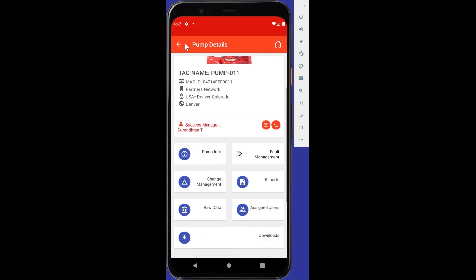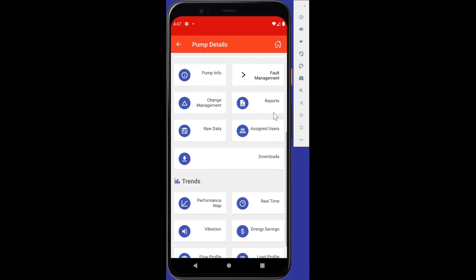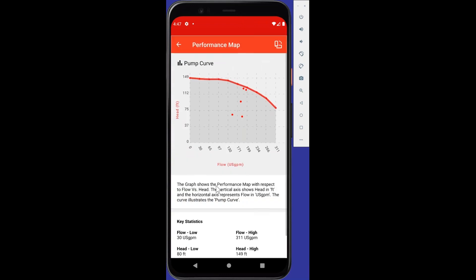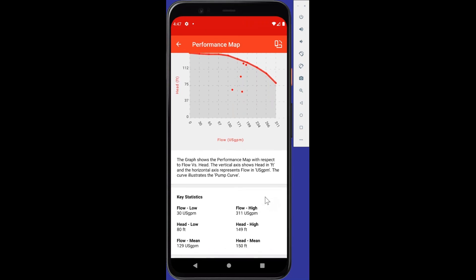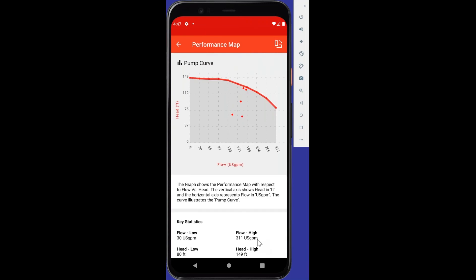I want to show you a few more features of the app. Let's scroll down to the performance map. So if I go ahead and hit performance map, we're going to show you the, well, we're all pump people on this call, the head versus flow curve map. As many of you know, our pumps send data to our cloud every five minutes. So on the graph there, you see five dots. So that's roughly what that pump's been doing over the last 25 minutes. Is my math right? Five times five is 25. Over the last 25 minutes. We see here some key statistics around the lowest flow and the highest flow and the lowest head and the highest head and the mean flow over the last little period of time. And for the pump curve, that, of course, is the 100% speed curve.